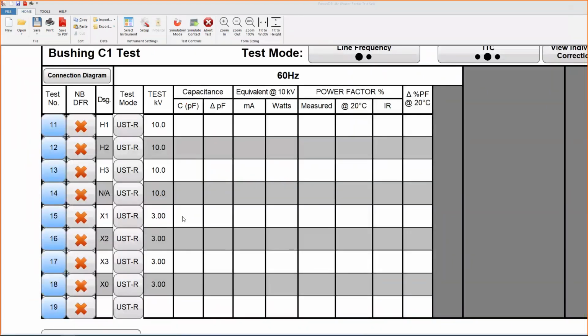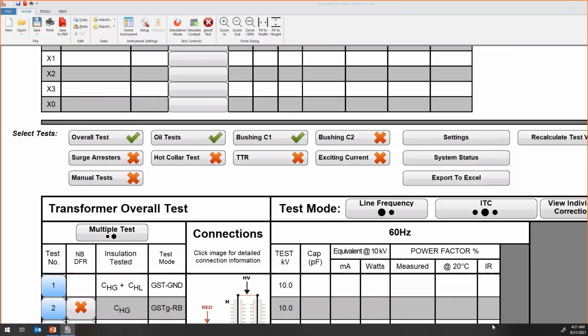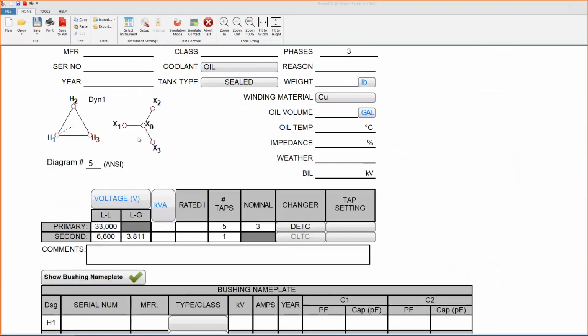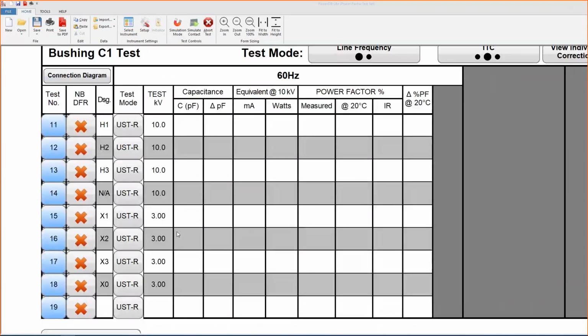Yeah, and perhaps if we look at this PowerDB form, if I put in the voltages as we discussed, 33,000 to 6,600 volts, and look at the test voltage that we want to apply to a particular bushing, we don't want to exceed the rating of that bushing. So perhaps he means 10 kV on the primary bushing and 3 kV on the secondary bushing. But yeah, I would like some additional information, or to be able to have an email back and forth with this particular customer so we can more accurately answer his question.